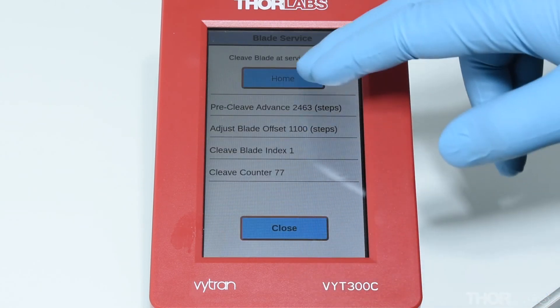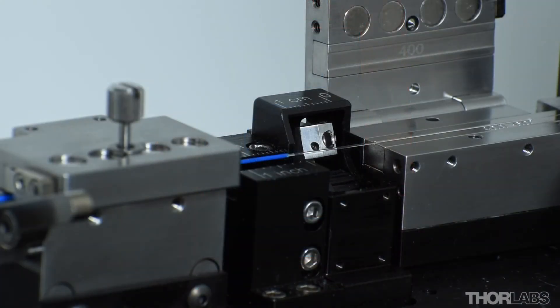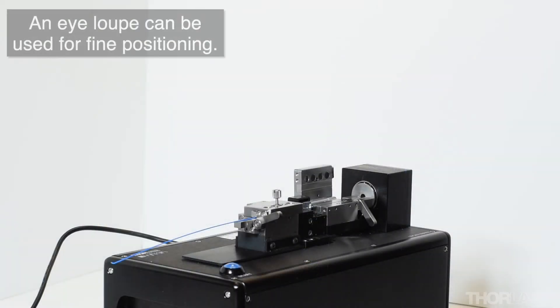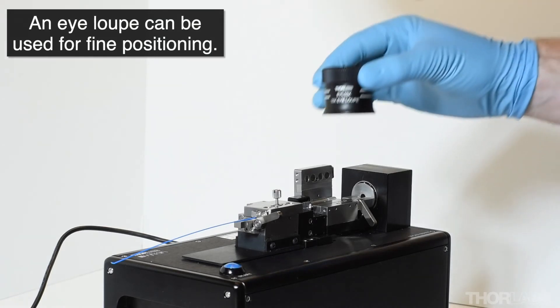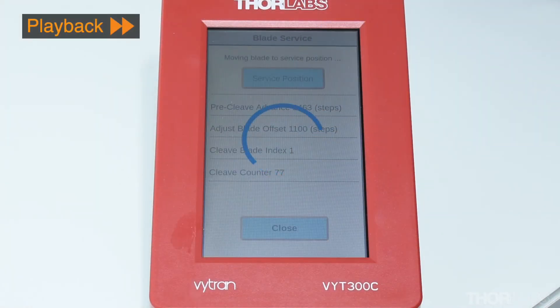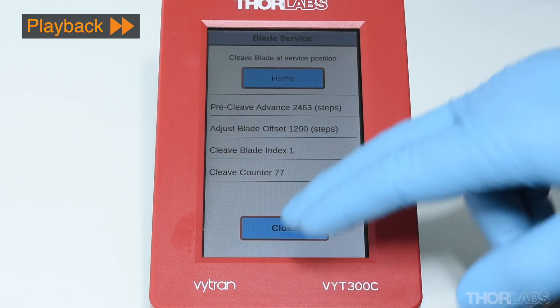Use the handset controller to home the cleave blade. Once the new blade offset has been set, move the blade to the service position once again and observe the end position of the blade relative to the reference fiber. It may be helpful when making fine adjustments and determining when the blade first hits the fiber to use an eye loupe. Some iteration will be required to achieve a blade offset that brings the blade close to, but not touching, the fiber.